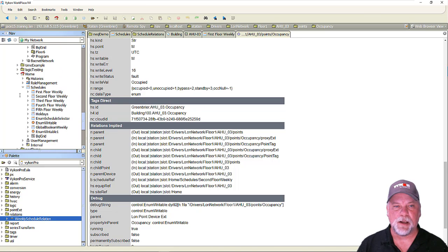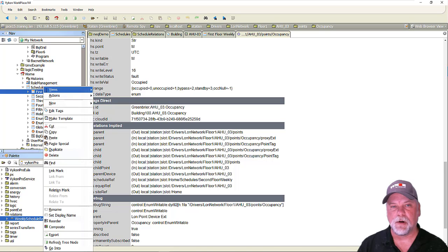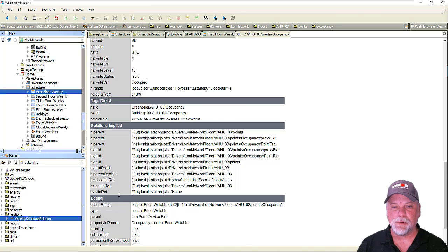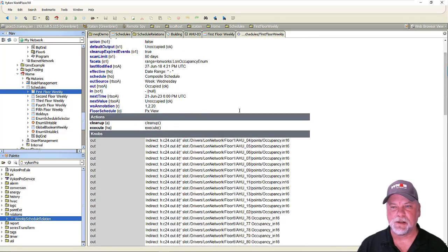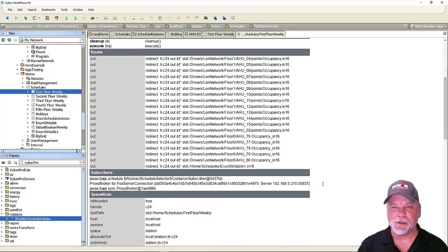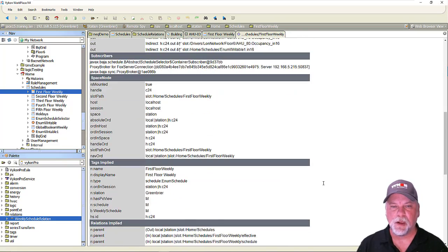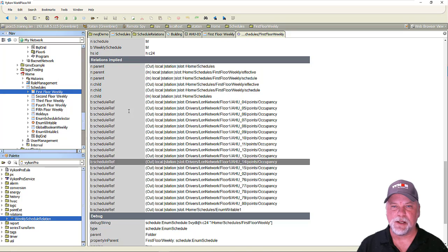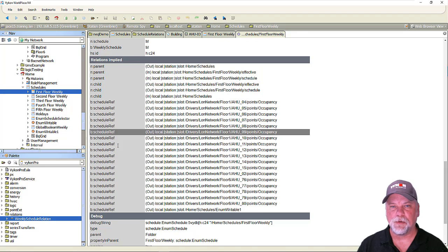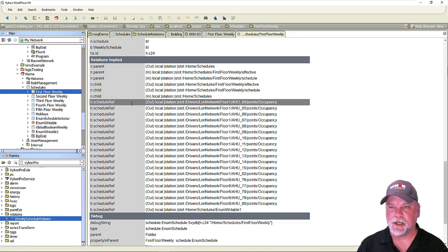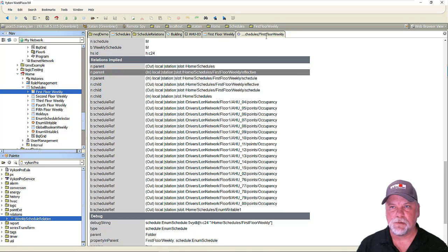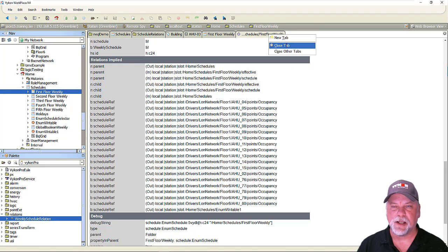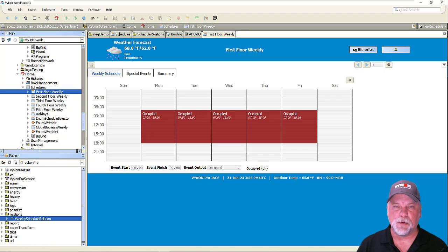And if I take a look at the Spy remote view on one of the schedules, we should see it has obviously the knobs, which are the data links that are going out to the actual occupancy points or schedule selectors and so forth. And then if I look at the relations, you'll see that this schedule has a number of outbound bScheduleRef relations out to various control points in the station. So that is just proving that that smart relation exists both from an inbound and an outbound perspective.